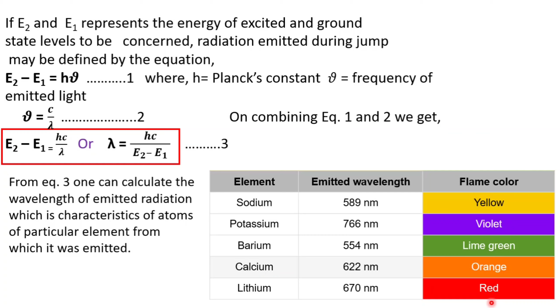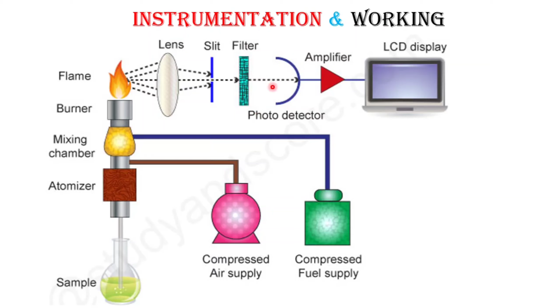Instrumentation and working. When the sample is aspirated into the nebulizer, it is converted into mist form and then sent into the mixing chamber. This mixing chamber is connected with a supply of compressed air and fuel, which helps in the production of flame. When the mist form of the sample is sprayed over the flame, the steps involved in the principle happen, and the emitted light is passed through the lens, followed by the monochromator. Depending upon the intensity of the emitted light, the detector detects it and generates a current. Due to the formation of an electrical signal, the data is recorded on an LCD display. Here, instead of a monochromator, we are using a filter.